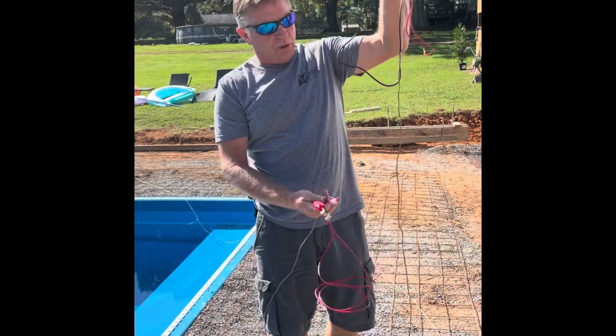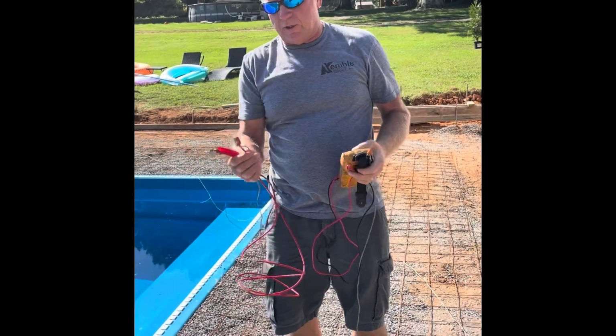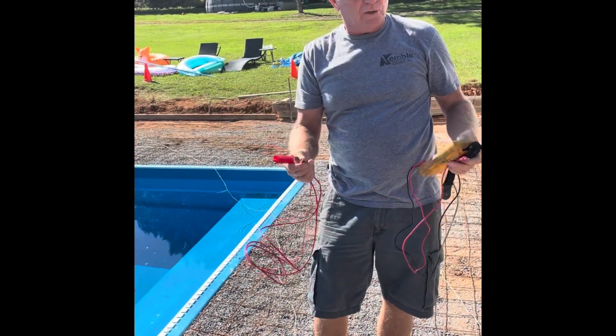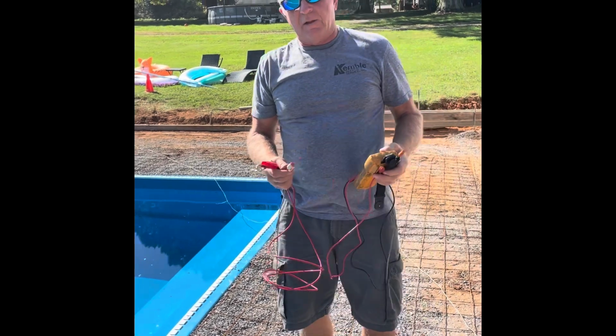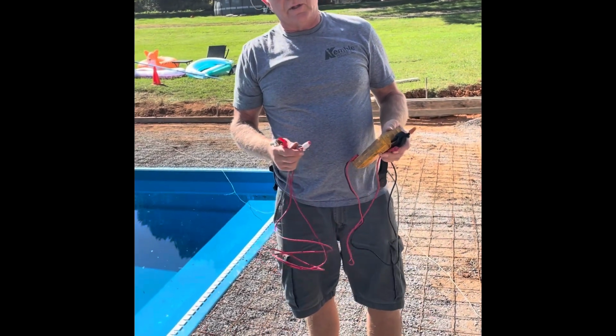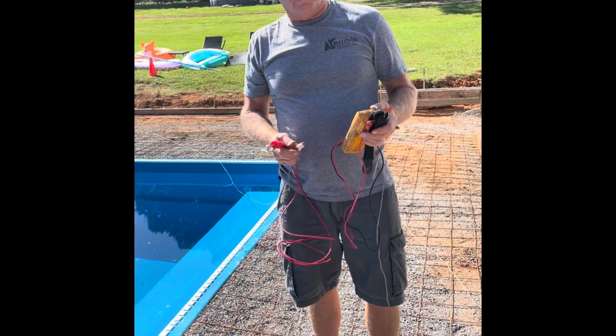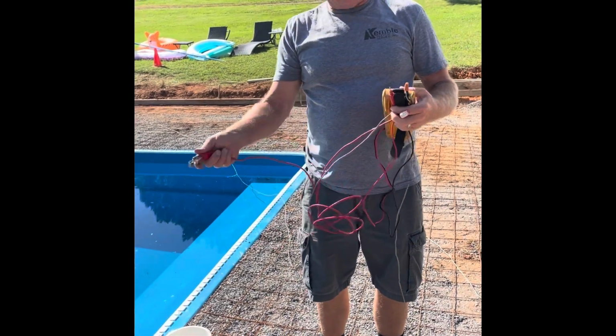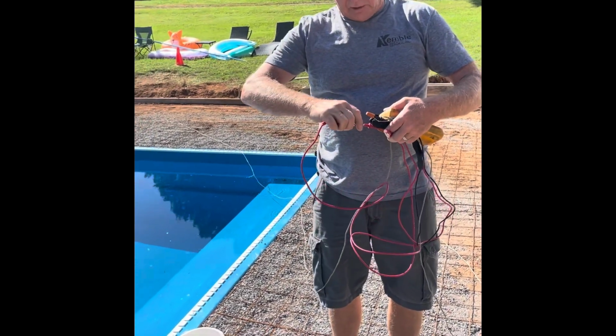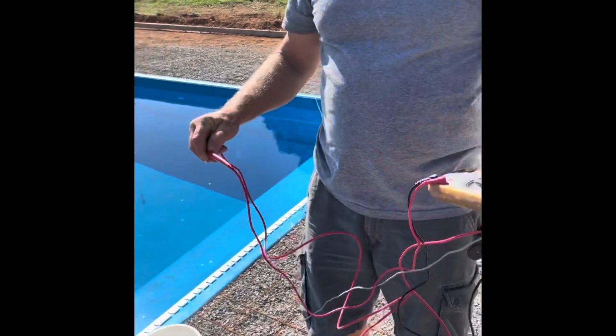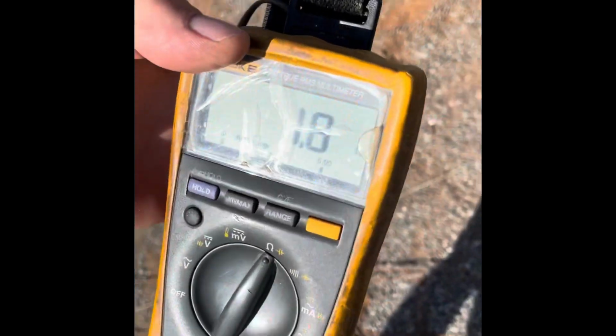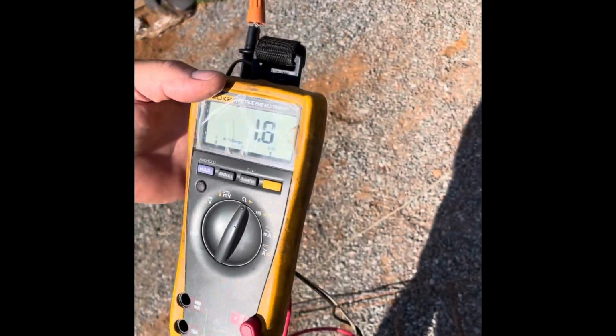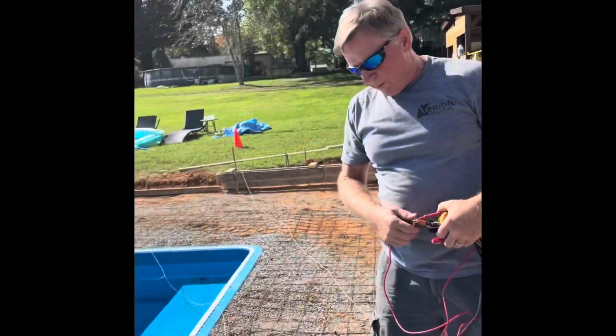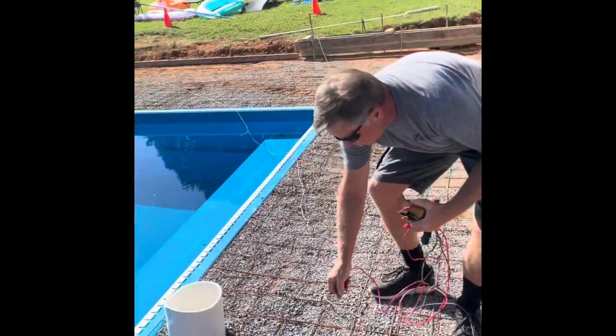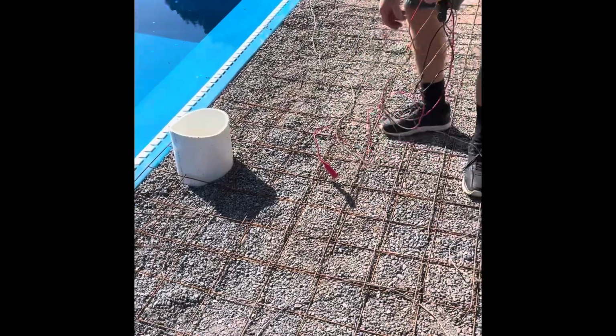Stick around. First thing we've done is we've created an extra long test lead. In this case, we've just used 4 conductor, 22 gauge wire, a couple 100 feet of it. The length of it's not really important. The size of the wire is not really important. What's important is that you check continuity from one end to another after you've made your alligator clips together. Check to see what your value is, and then we're looking for the same value as we go around this swimming pool from every one of the split bolts to the next one.